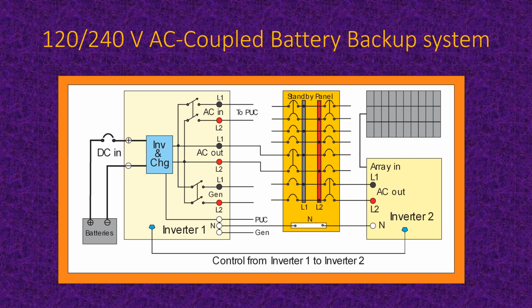We did have, for example, a utility feed coming down with the utility meter on the wall of a house that was near the swimming pool and us on that side. And we decided we are not going to mess with that meter. We're not going to try to get in there. We are going to put all of our equipment on another part of the house and feed the PV into the main panel. Actually, I think we put a separate junction box next to the main meter and rerouted the main meter feed through that junction box so we could tie in the solar there. So there are many ways to do this in terms of tying into the utility. They are all listed in National Electrical Code, Article 705.12.